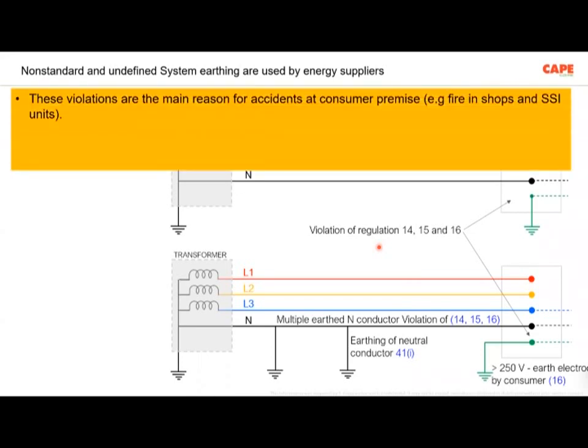instead of a TN-S system. Say, for example, in hospitals, there are hospitals that have multiple low voltage supplies. I have seen a hospital a year back. They have 4 connections, 4 LT connections, and there are a few operation theaters as well in the hospital. So what happens, if because of the violation from the electricity supply company, due to an earth fault, let us say, for example, in the video which we have seen, the ventilator started the fire. Your protective device will not trip.